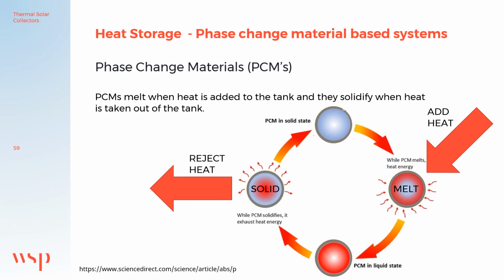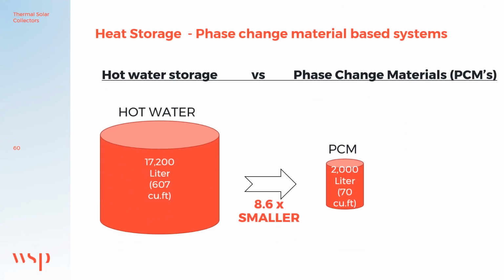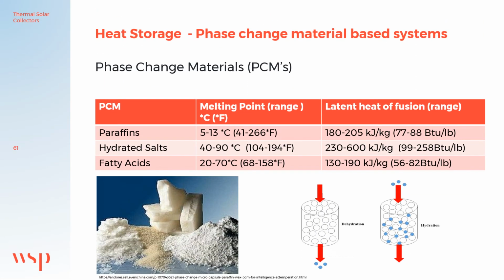Another type of thermal storage is by making use of phase change materials, or PCMs. PCMs melt when heat is added to the tank and they solidify when heat is taken out of the tank. One of the main advantages of a phase change material is that it takes up approximately 8 times less space than a conventional hot water storage system. Common PCMs for heat storage in solar cooling applications are paraffins, fatty acids, and hydrated salts. This table gives an overview of the physical properties.